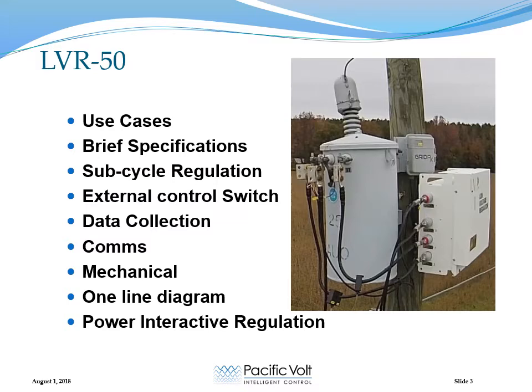Today we are discussing a 50 kVA residential low voltage regulator which operates on the secondary side of the distribution transformer. In North America, utilities would call this a single-phase service, although more correctly, the regulator is a split-phase design for a three-wire service.